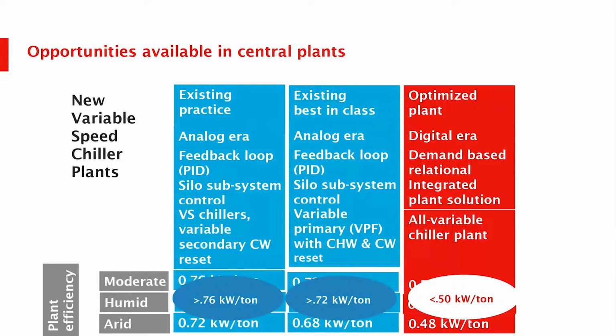But what does it mean from a perspective of what you can actually get out of a plant? The efficiency of a plant is largely dependent not just on the load, but on the outdoor wet bulb. So I'm a little reluctant to say here's what the best-in-class efficiency number looks like, because it's really highly dependent on the prevailing weather conditions—so we kind of have a range.